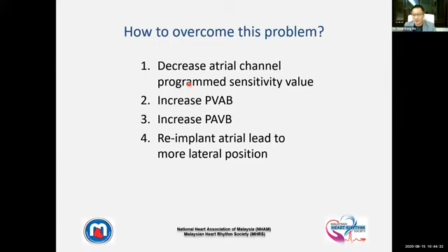The answer is PVAB. Now, why not decrease the atrial channel programmed sensitivity value? It's the opposite. You should increase the value. You increase the value, you decrease the sensitivity. It's a bit counterintuitive here. Increase the value. Let's move on and go to the final case here.